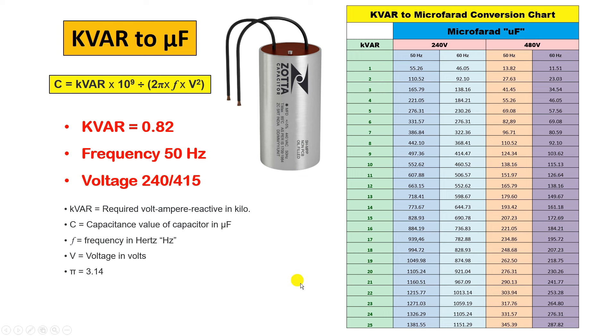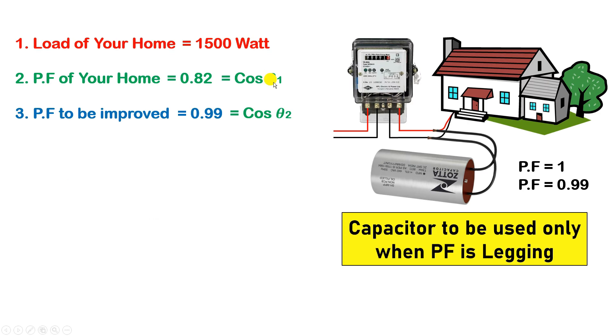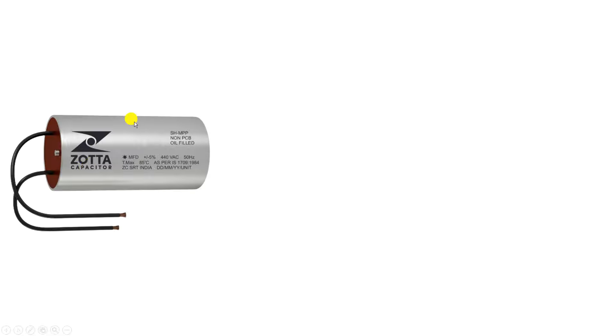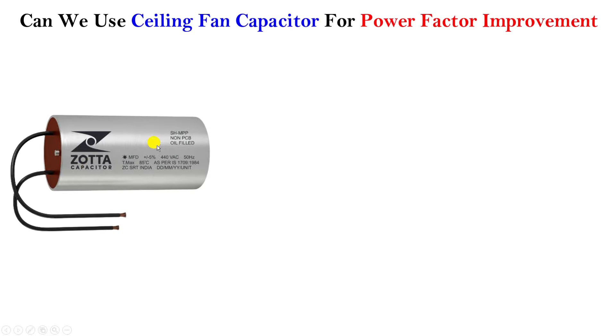To summarize: for a 1500 watt home load with power factor 0.82, to improve it to 0.99, we need at least a 40 microfarad capacitor. Now, can we use the capacitor from a ceiling fan for this purpose? The answer is no — a ceiling fan capacitor is not designed for continuous use with heavy load for power factor improvement. Connecting it may cause it to blast.